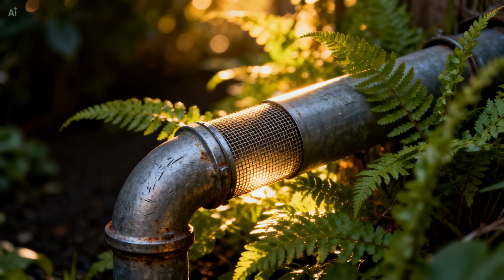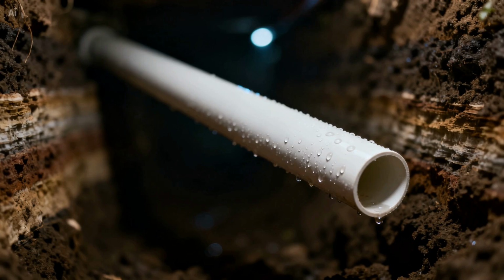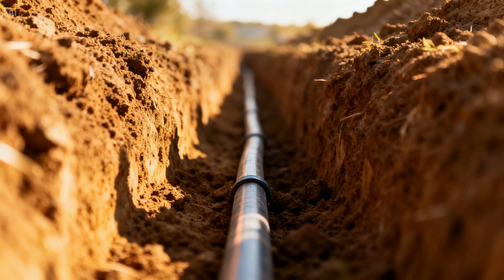The intake end of the pipe is positioned outdoors in a shaded area on the north or east side of the building. Shade prevents solar preheating of the incoming air before it enters the tube. A screened cap prevents insects, rodents, and debris from entering the system. The pipe runs underground at a depth of 6 to 8 feet, sloping gently at a 1 to 2% grade from the midpoint toward both ends to allow any internal condensation to drain out by gravity rather than pooling inside the tube. The length of the buried section determines the cooling capacity.